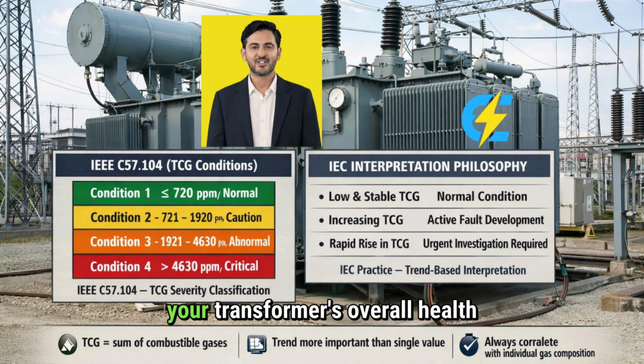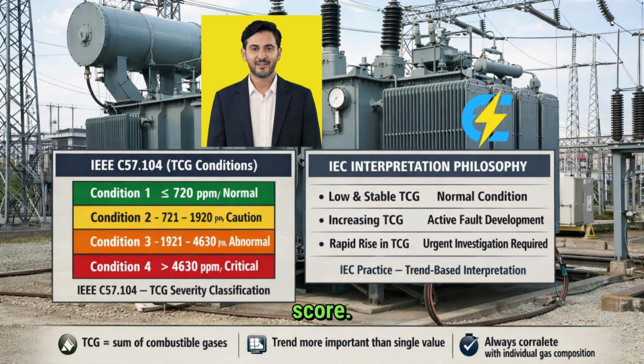Think of TCG as your transformer's overall health score. It doesn't tell you which fault is happening, but it tells you how serious the situation is. When you're standing in front of a transformer at 2 in the morning with the DGA report in your hand, TCG is what helps you decide whether you can wait until morning or need to call the emergency crew right now. The beauty of TCG lies in its simplicity for risk ranking.